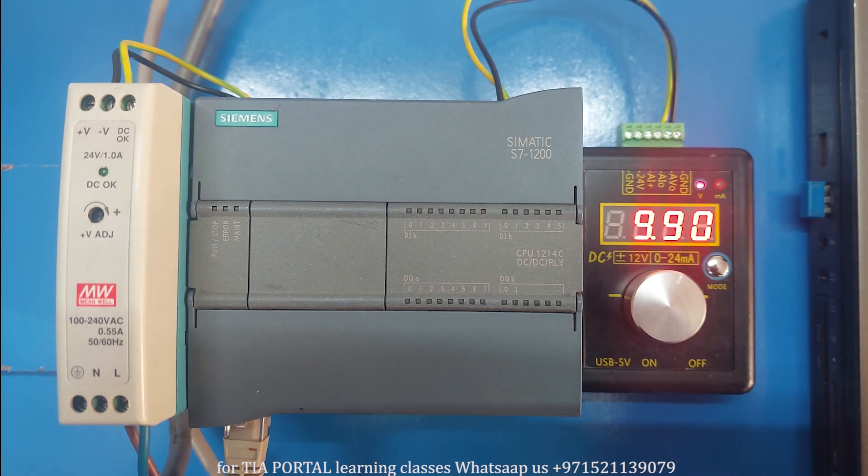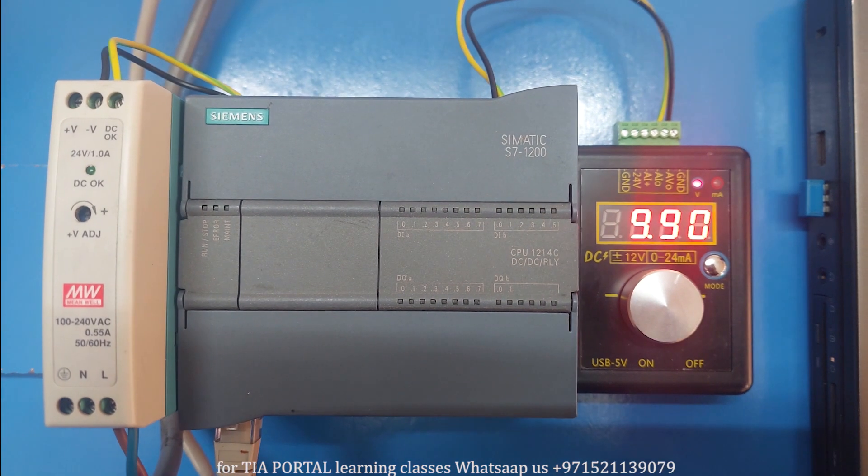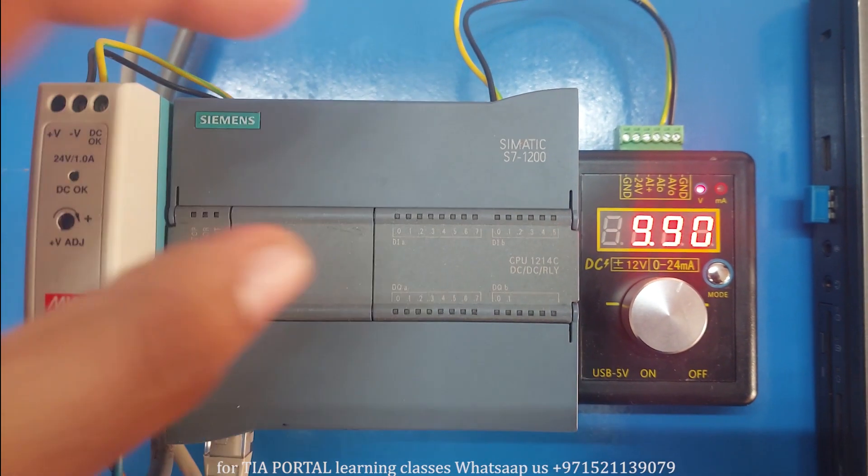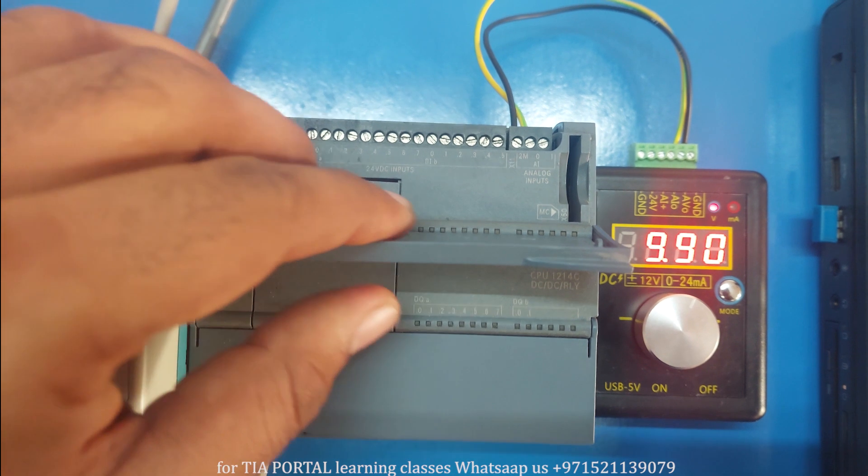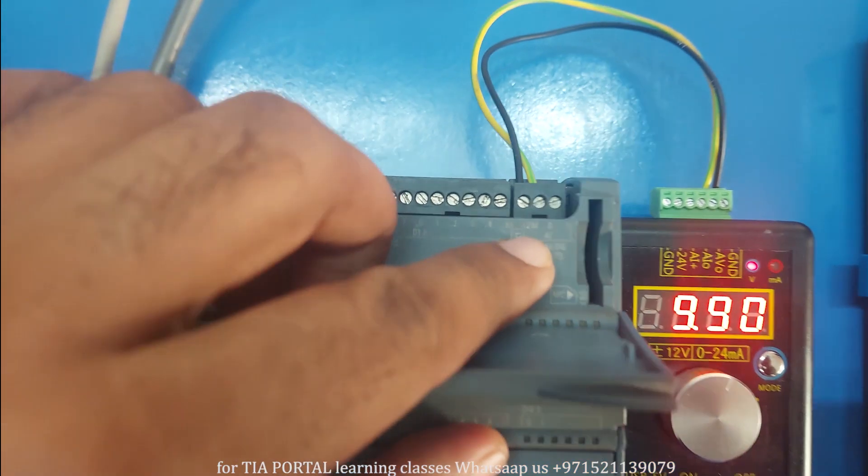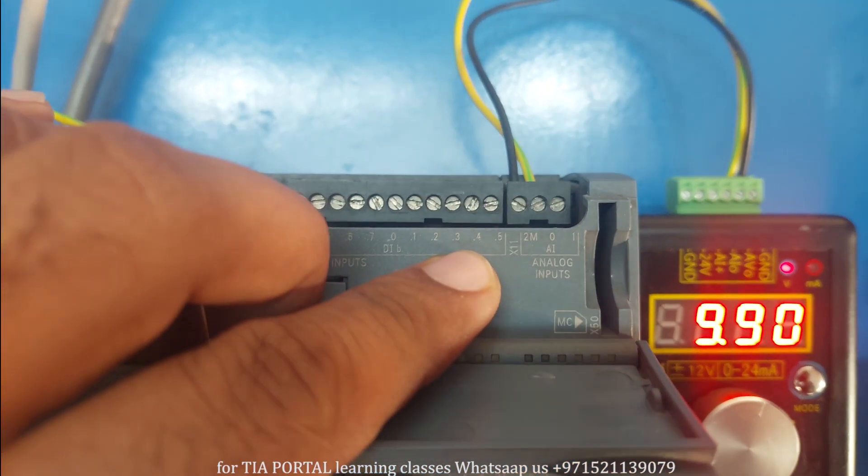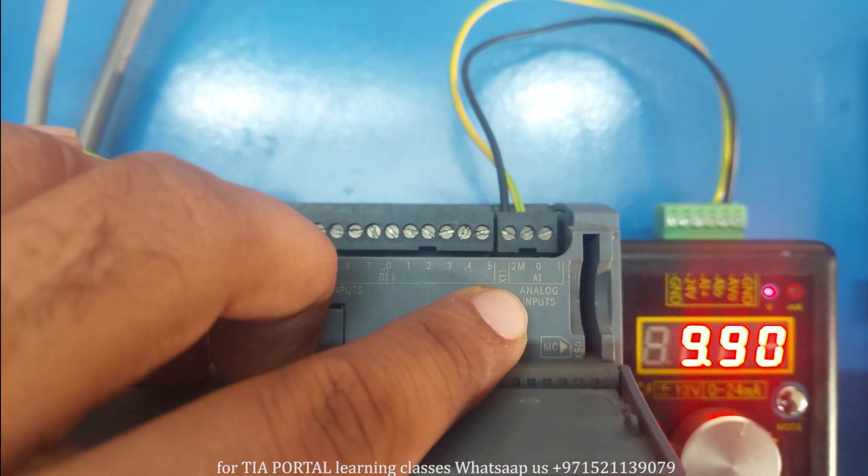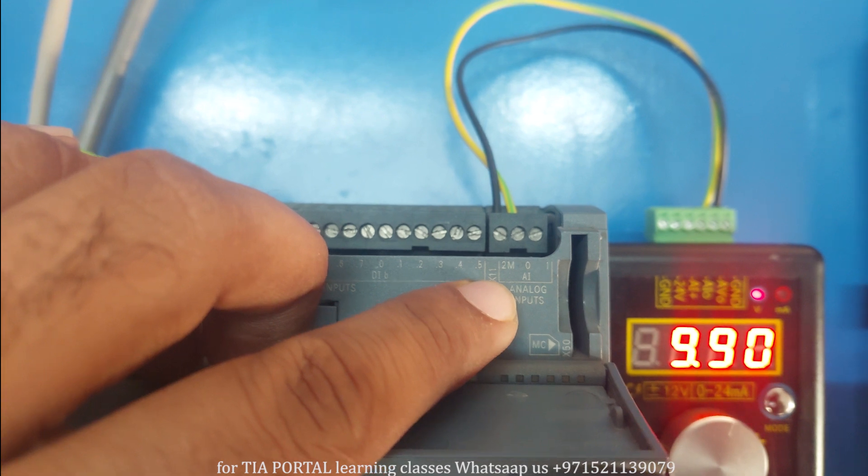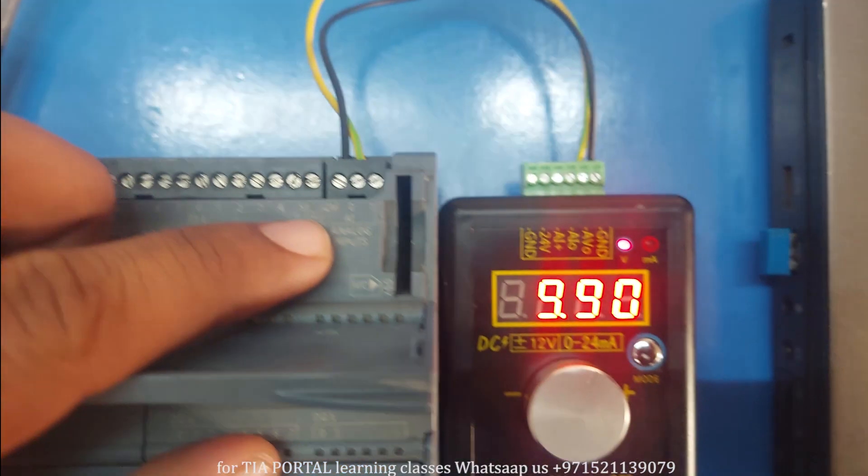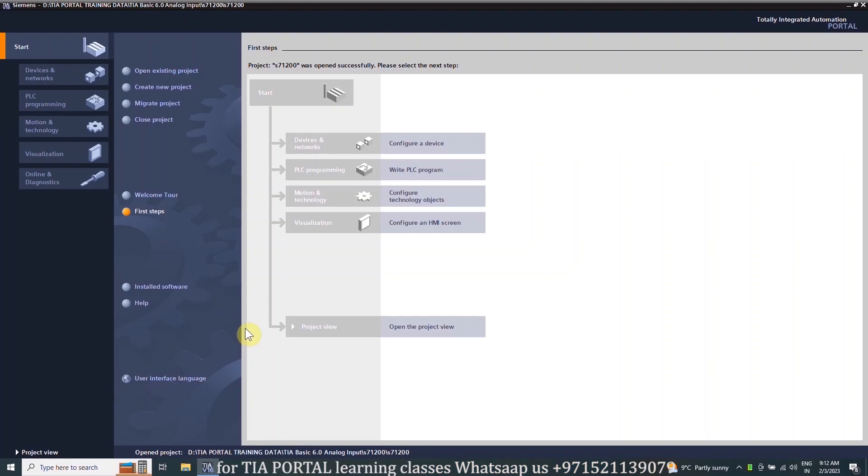As you can see, today we have an S7-1200 PLC and we have connected an analog signal generator with it. We have connected the 0 to 10 volts analog output of the signal generator to the analog input channel 0 of the S7-1200 PLC. Now let's go to the TIA Portal software and see how we can make a program to read that analog signal and how we can scale this signal into some usable values.